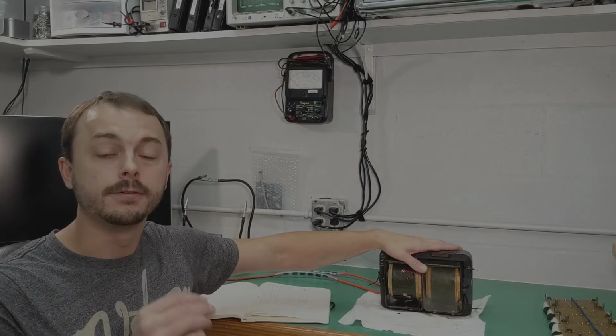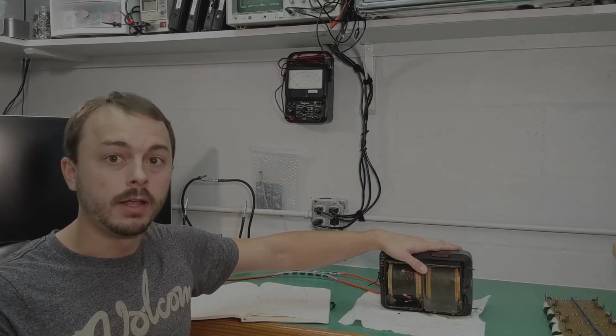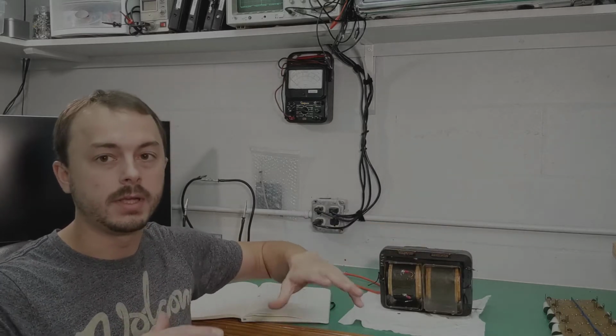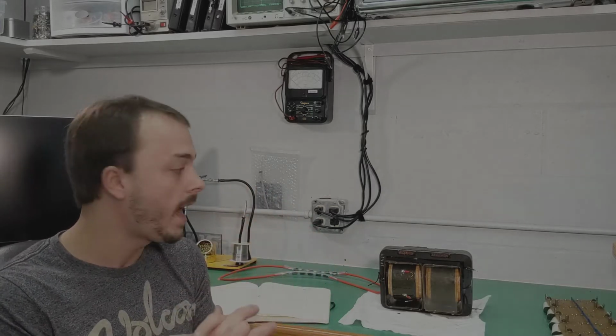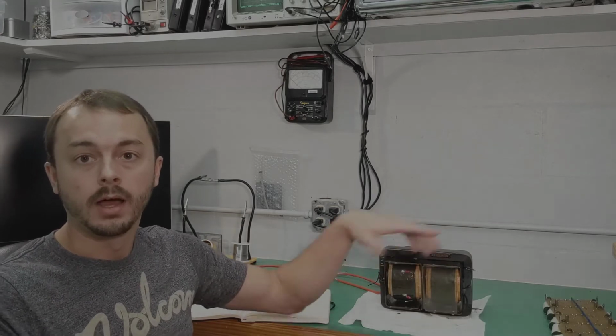We need negative high voltage output in relation to our grounded DC, because the outside of our fusion chamber is going to be ground and the internal grid is going to be at a negative 50,000 volt potential. I'll show you how we're going to wire this up in that configuration.